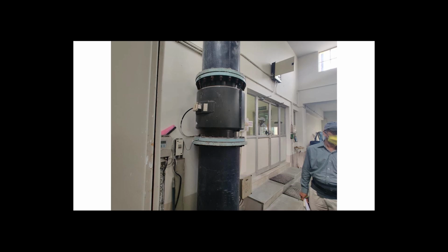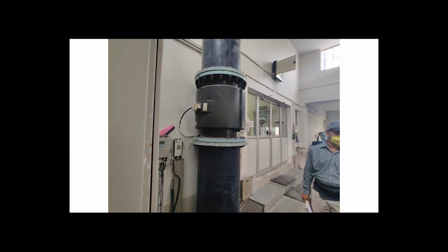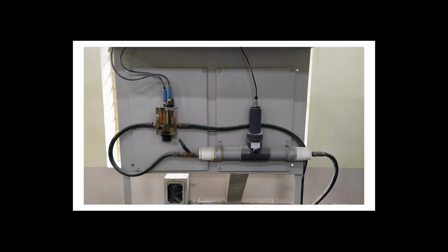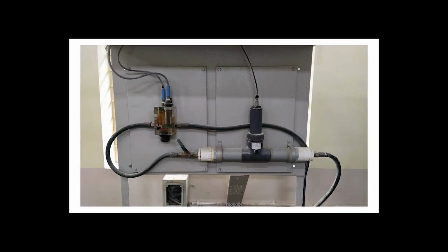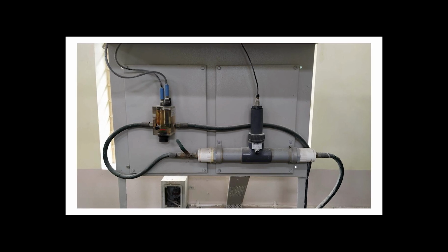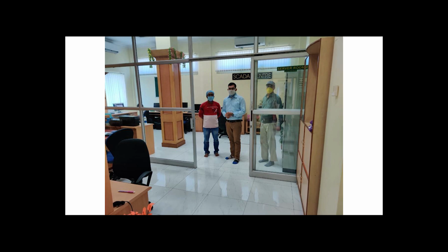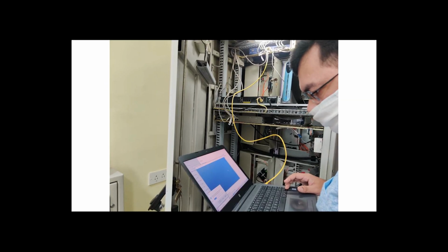The system adopted was to transfer the data from the instrument to the monitoring station at a remote location through text message. It was designed to be transferred through mobile SIM. Each instrument location, type of measuring parameter, time step, value data and other relevant information were codified as a unique entity. This data had to be transferred to the remote monitoring station at 2-minute intervals. This raw data was then decoded at the monitoring station through a software program and analyzed.